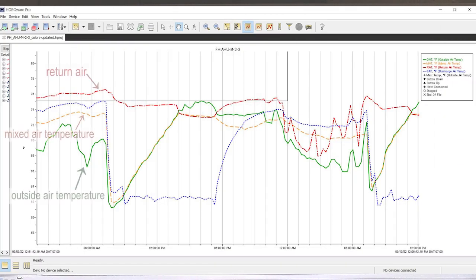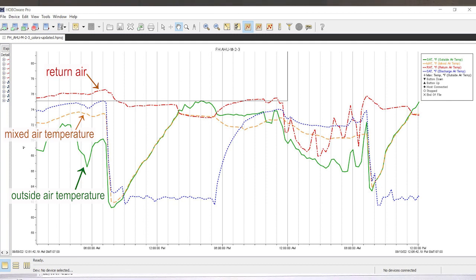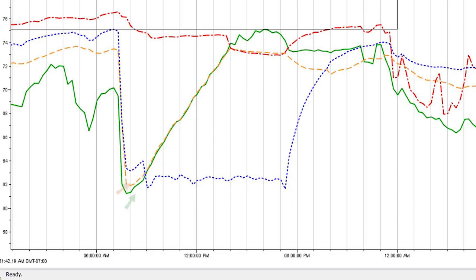So I have my data from the data loggers pulled in here to our HoboWare Pro software, and I've got the specific day we were just looking at in the BAS trend logs pulled up here. So you can see as the system starts to ramp up for the day, the green line represents the outside air temperature. You can see that we're starting to let in as the outside air damper opens.